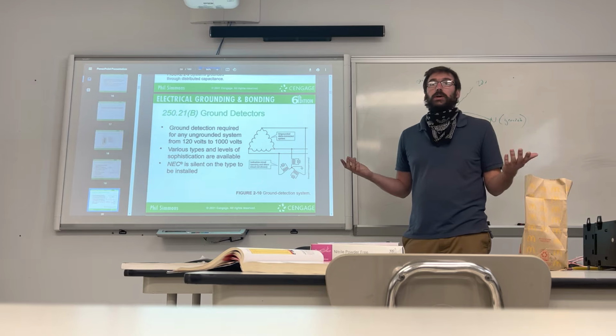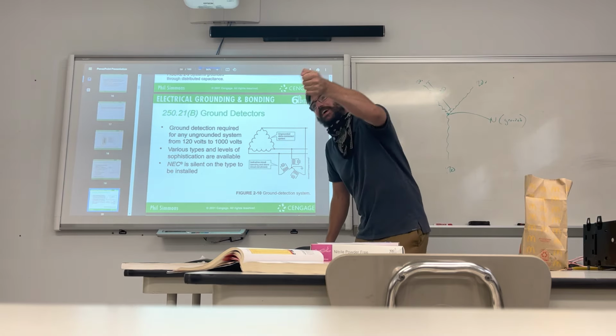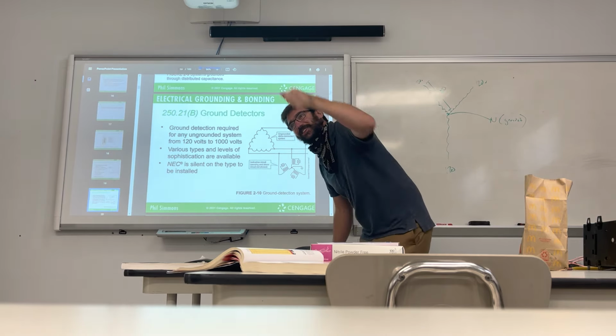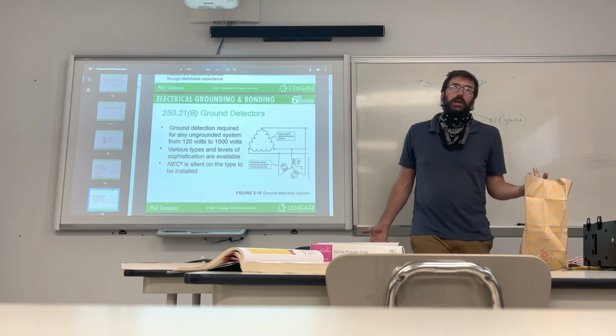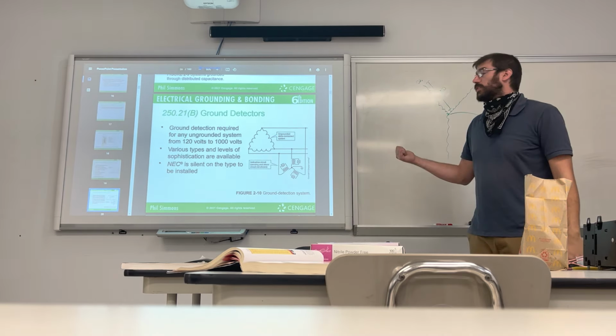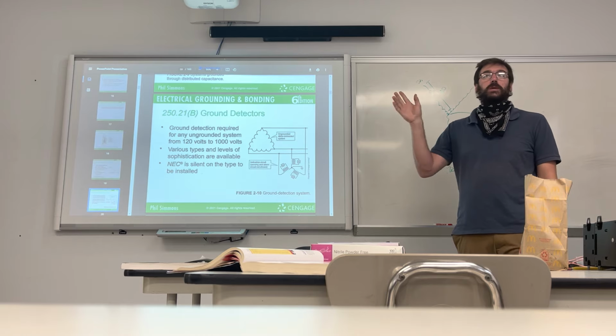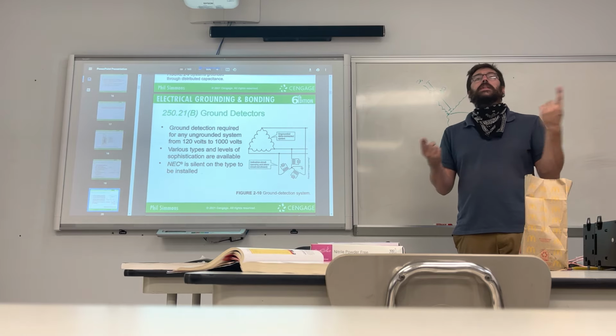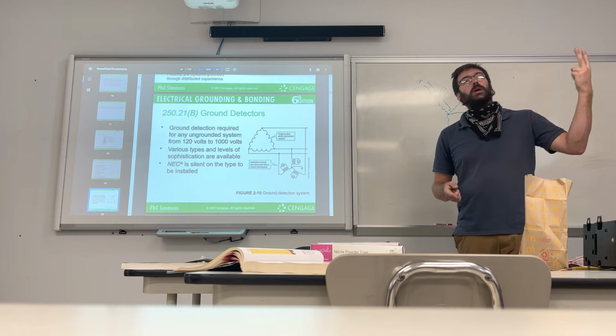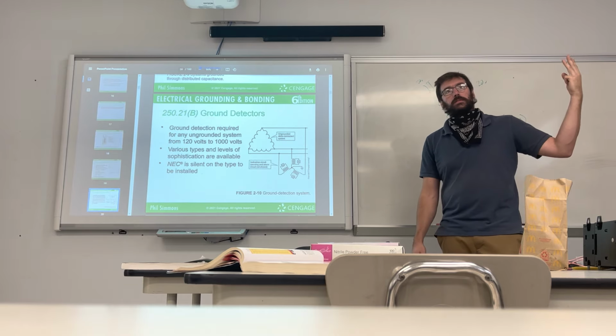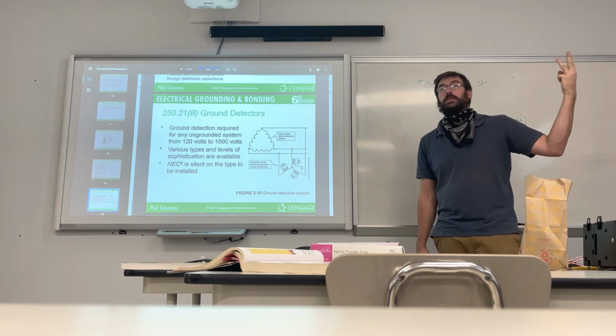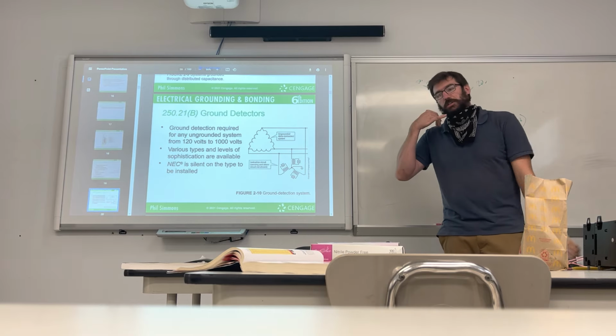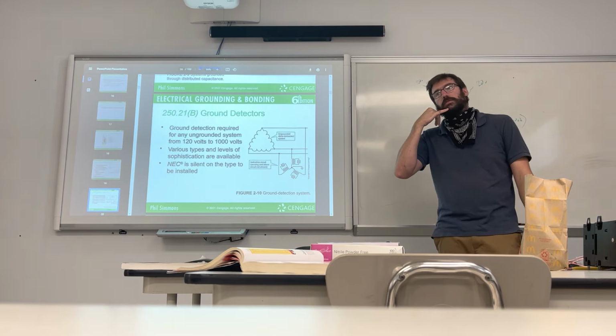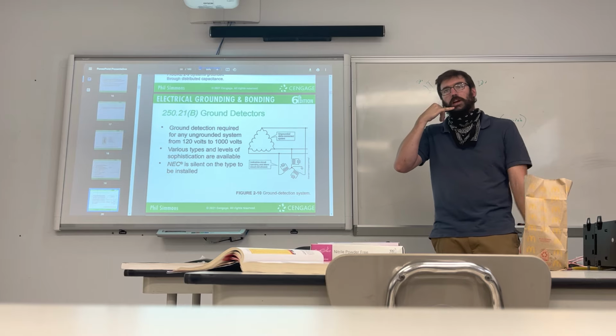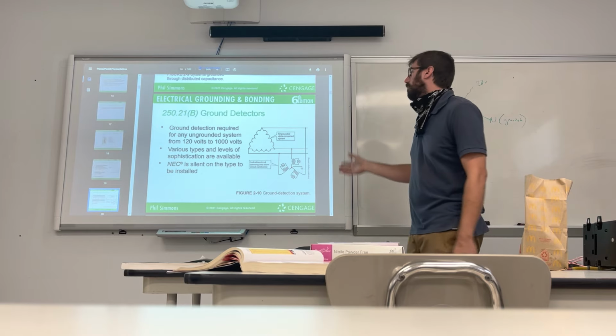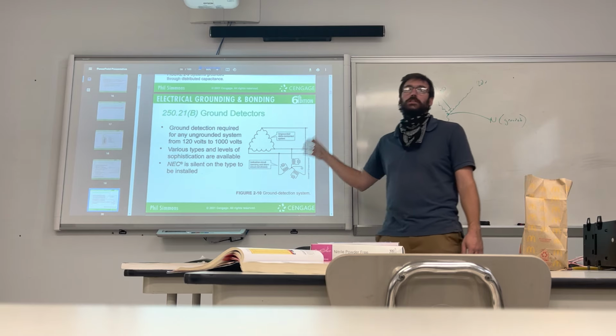How do you think we would figure that out? Do you think there's a guy there with a meter just checking conduits all day, every day? No, there's an alarm in place. An alarm could just be a continuity detector. Once it detects voltage on the line, it just screams. It could turn on a light. It could turn on a horn. It can send a signal to a guy in a computer bay 1,000 miles away, saying, hey, we have trouble here. He calls up the electrician, hey, Unit 5 in Scranton, we have a ground, go and take care of it quick.